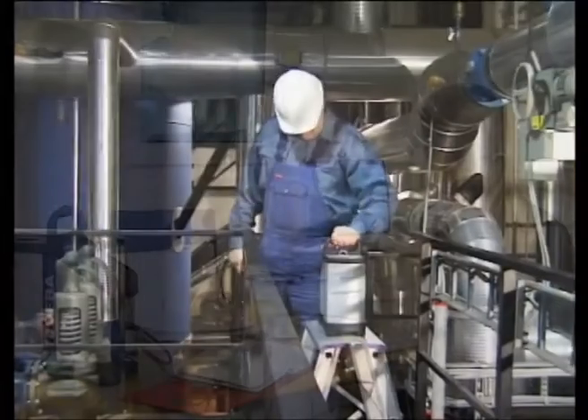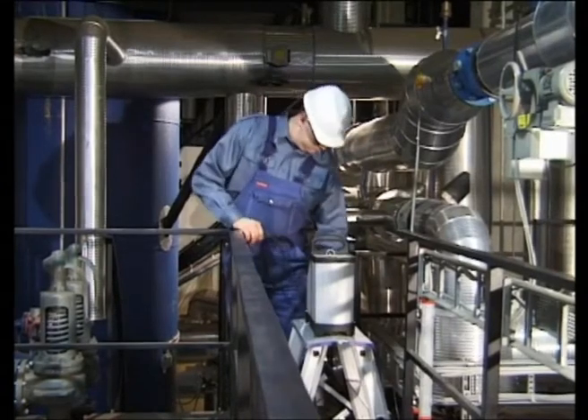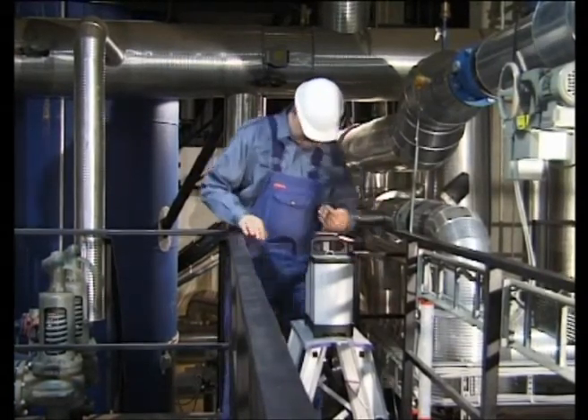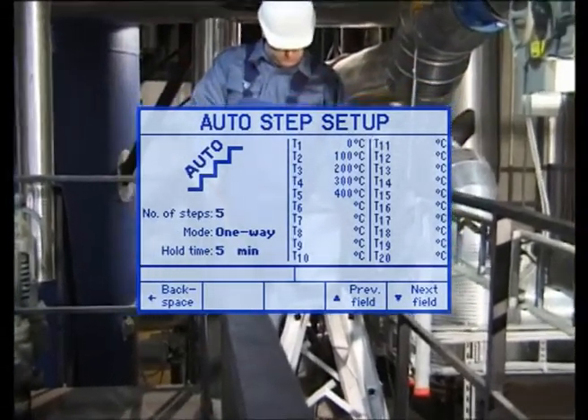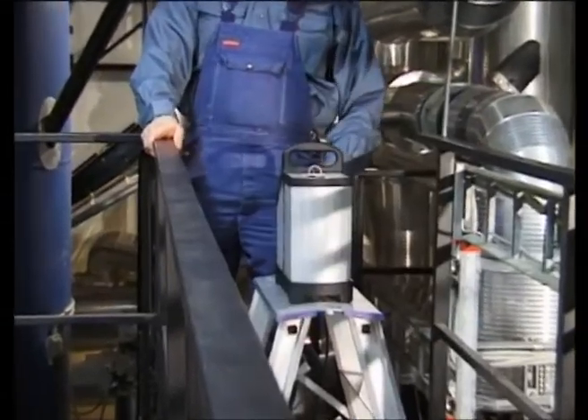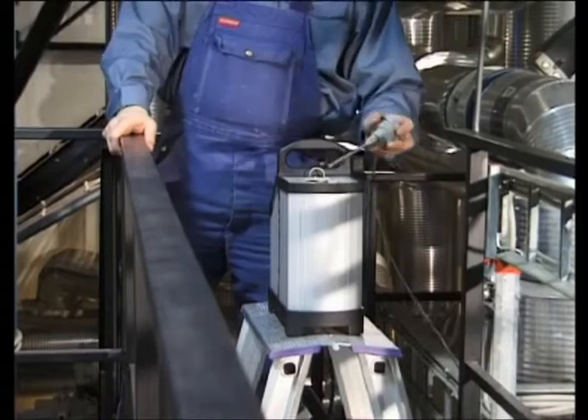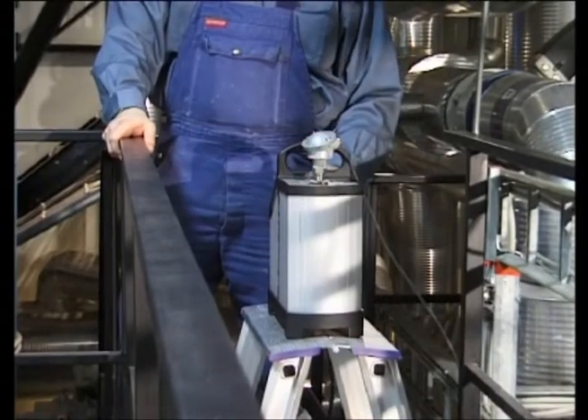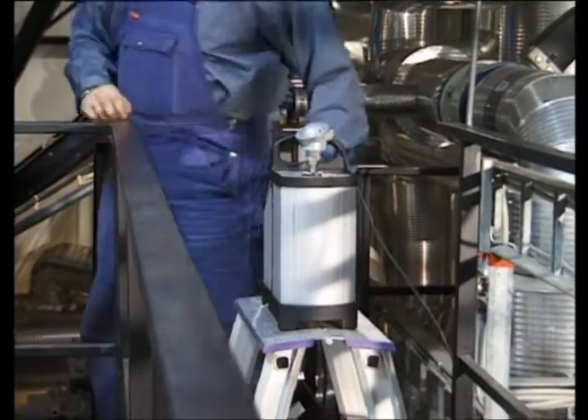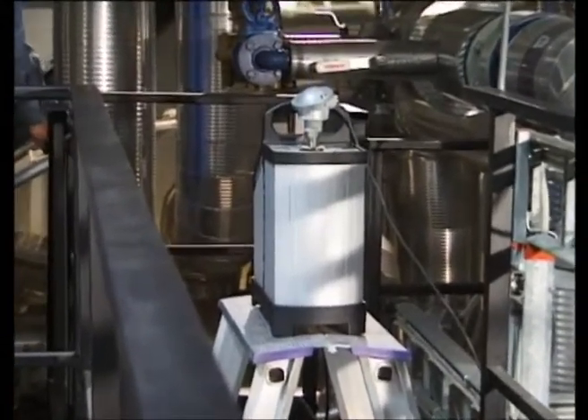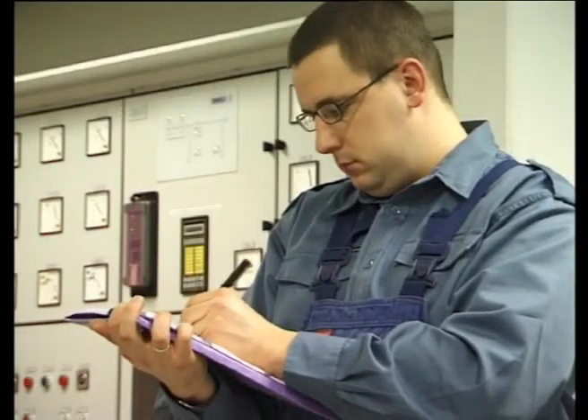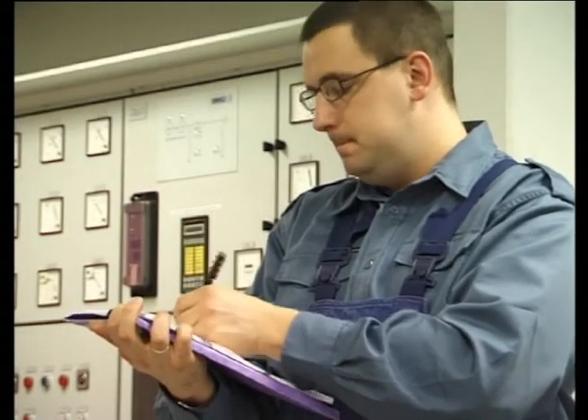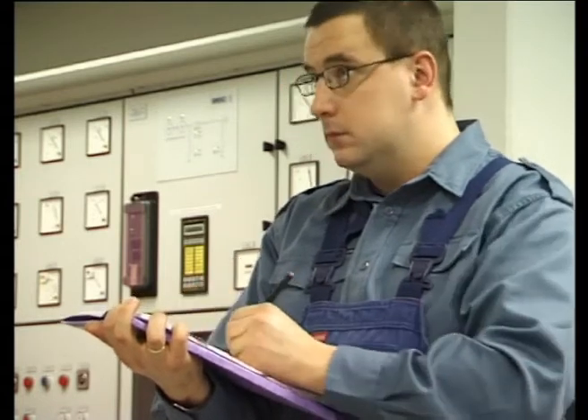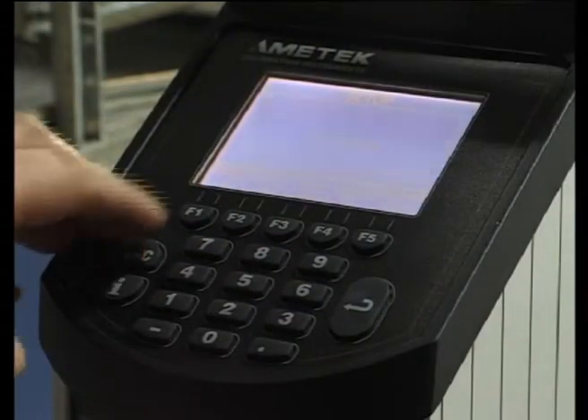The ATC series is also capable of performing automated calibrations without using the Amcal temperature software. Using the auto step function, the calibrator is able to change between a list of user-defined temperatures automatically. You define the temperature and the stability time required for each step. The calibrator is placed at the process line, thus allowing you to be at a distance, for example, in the control room, recording the values for the relevant sensor. Upon return to the calibrator, you can key in the results. Using the automatic thermostat test, the calibrator is able to determine the open, close, and hysteresis temperatures.